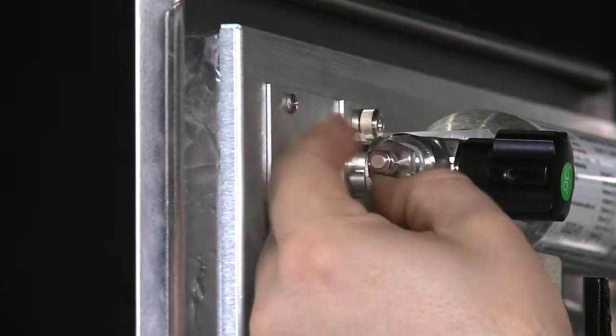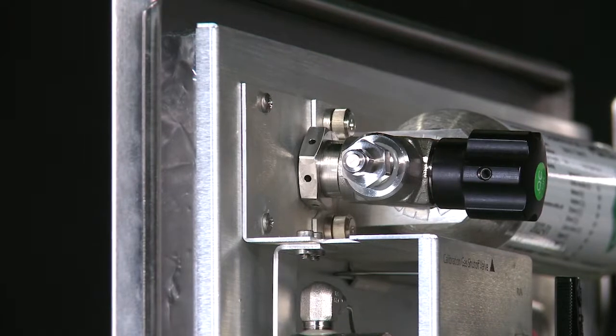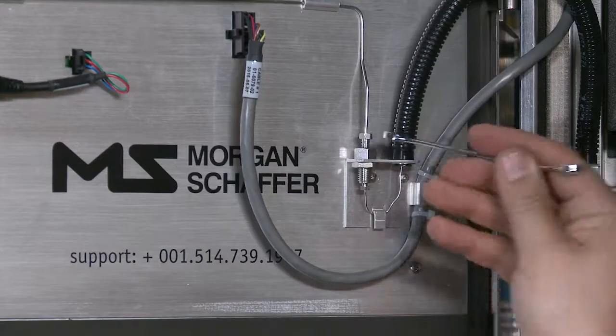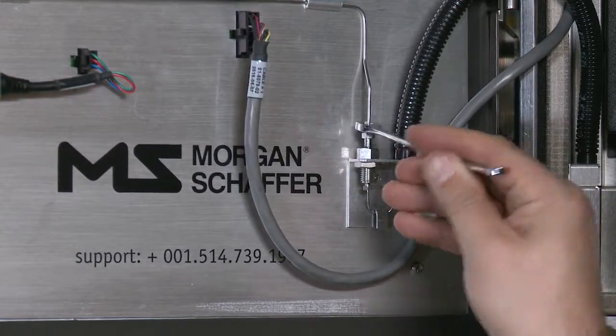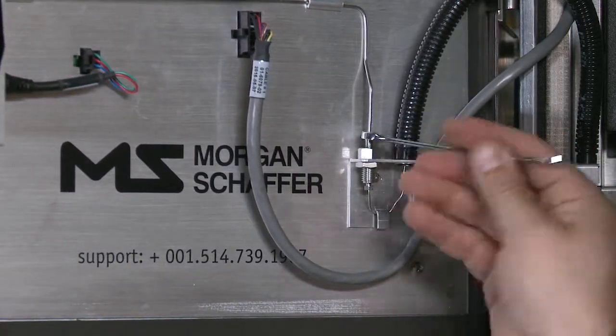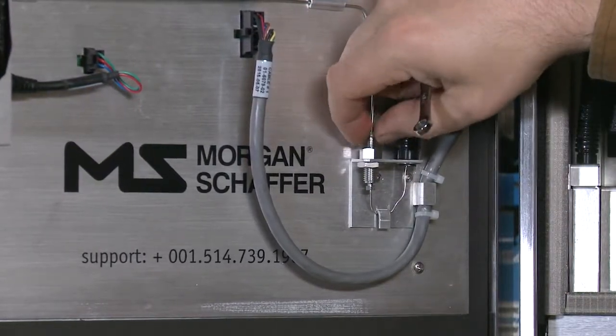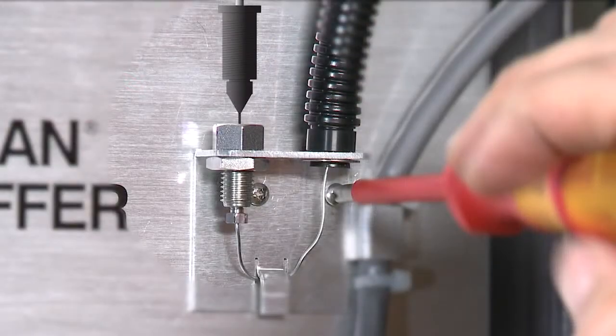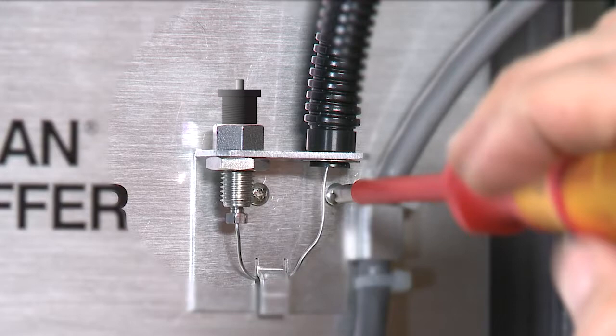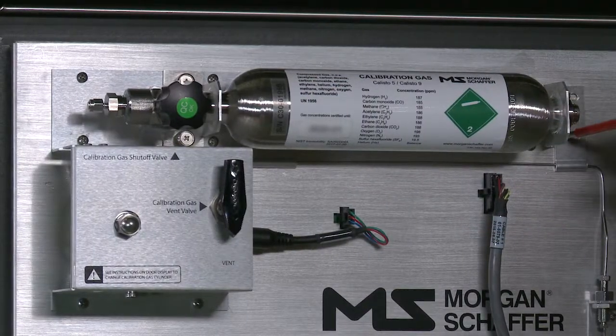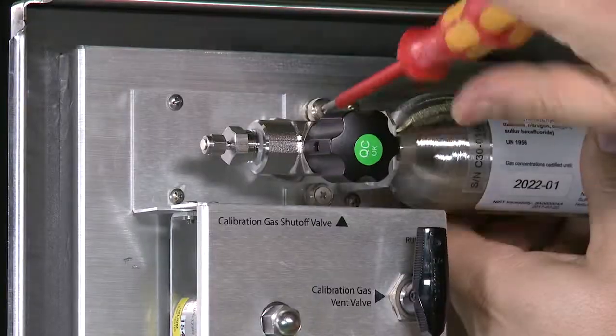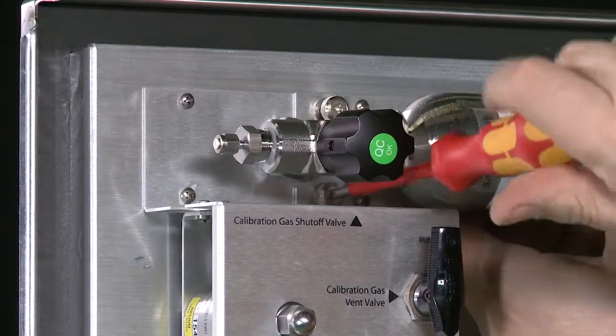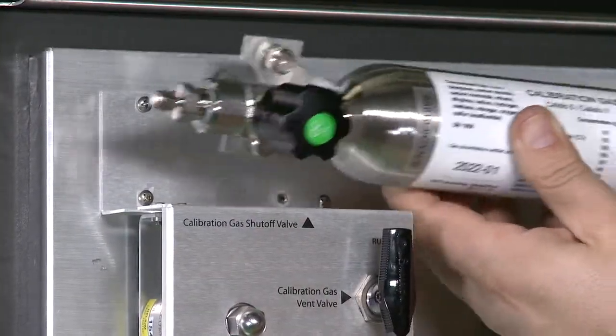If you are to reuse the same cylinder, immediately install a 1/16" male cap on the cylinder to prevent contamination. Screw finger tight only. Using a 1/4" wrench and a 7/16" counter wrench, remove the 1/16" OD calibration gas tube from the door fitting. Immediately install the supplied 1/16" male plug on the fitting body to prevent contamination. Screw finger tight only. Using a Phillips No. 2 screwdriver, loosen the 2 screws of the cylinder retainer. Loosen the 2 Phillips screws on either side of the shutoff valve and remove the calibration gas cylinder.